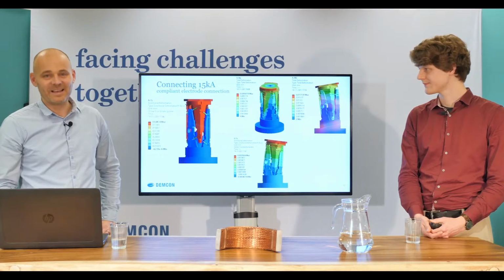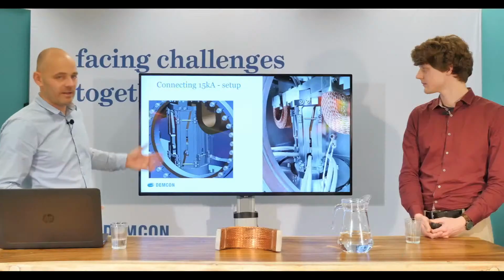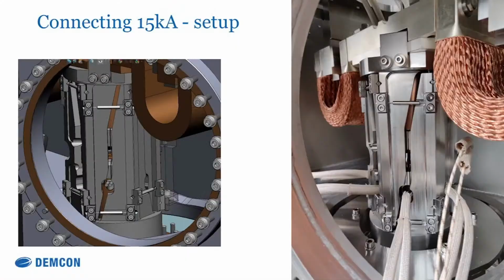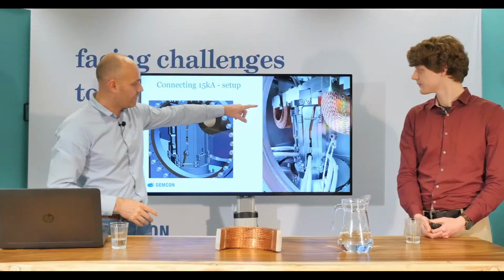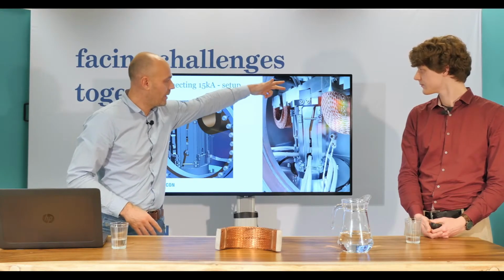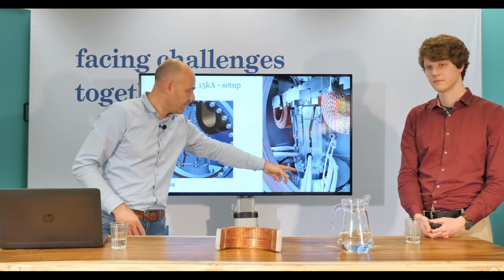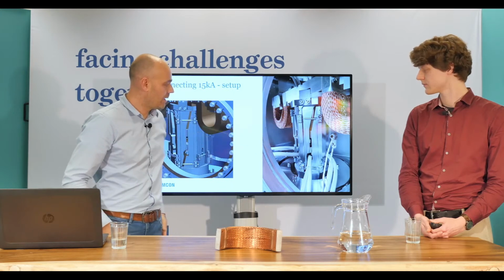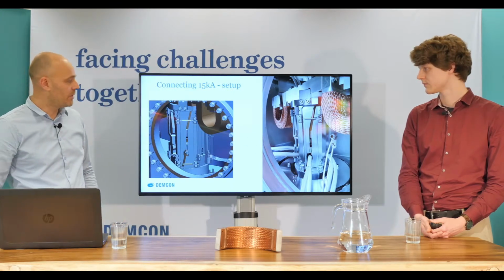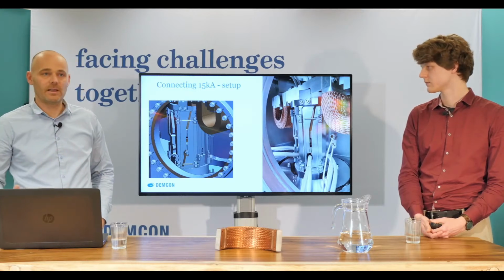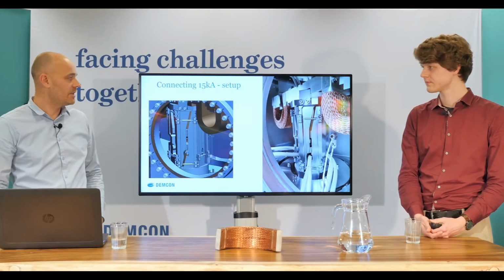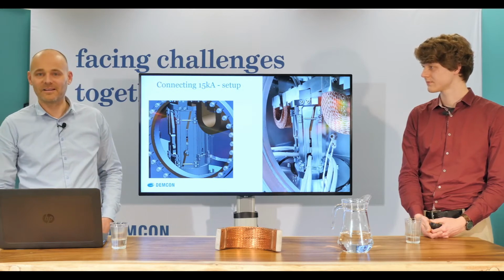So there was a lot of work and a lot of people working together to achieve all this. And this is the result in 3D, where we have, let's say, the expectation we have up front, and on the right the actual result of the manufactured part, which is in our lab here. You can see the braided copper parts, connection to the top electrode, part of the leaf spring in between, the bottom electrode with the connections to the heaters, and the actual leaf springs in between, which show you that by doing all these steps and doing all designs, making all the analysis, finding all the issues, you can make something which should be able to work at the end.